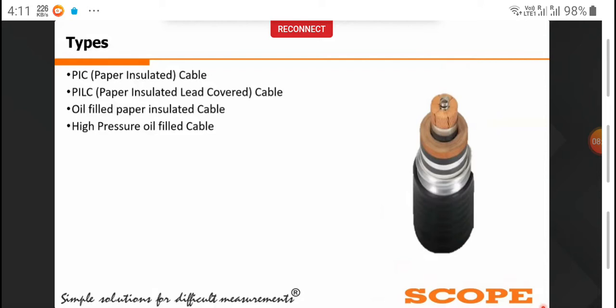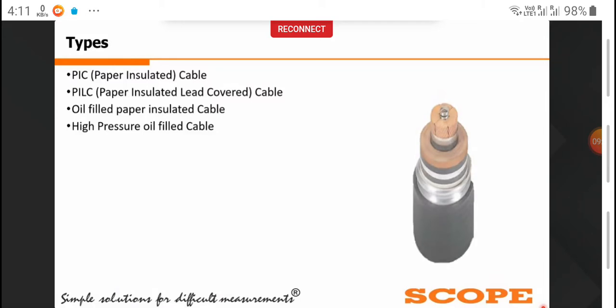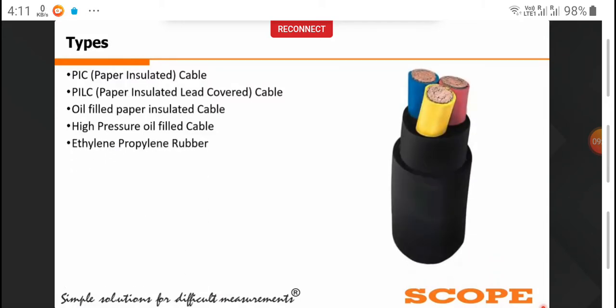These oil cooled cables are used for 66 kV and above applications. In this type of cable, the reservoirs mean maintenance, and we need to always keep the pressure constant, and also do frequent maintenance of this type of cable. To overcome these disadvantages of high maintenance cost, and because detection of oil leakage is also difficult in this type of cable, extruded cables were developed, such as ethylene propylene rubber.